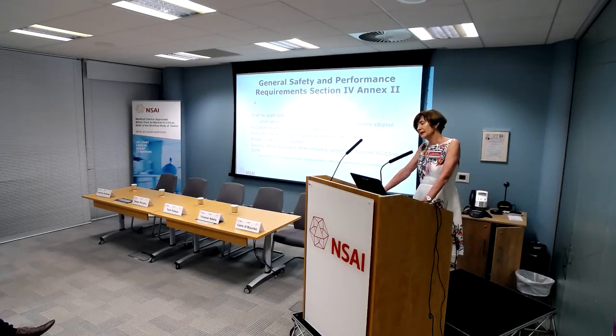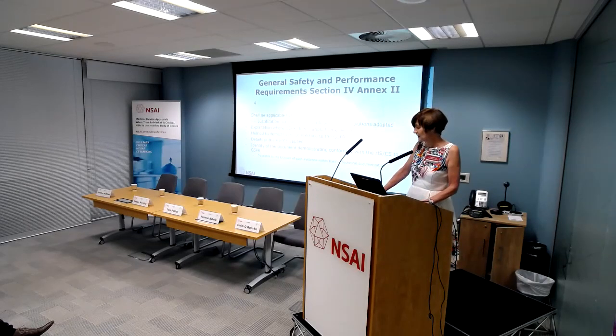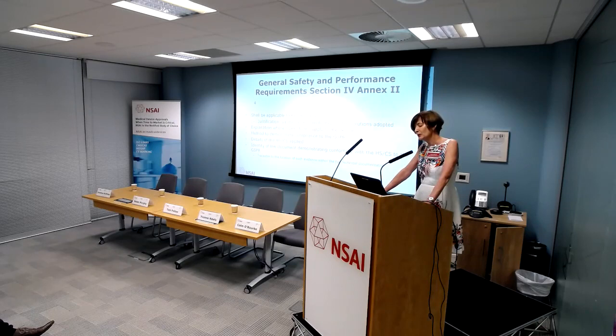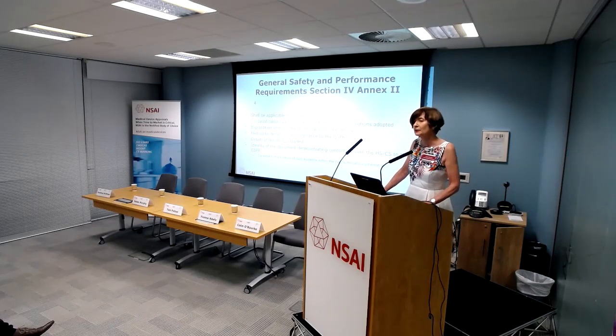You need to demonstrate the method, how you comply with the essential or the general safety requirements. You need to identify the harmonized standards and the common specifications that you have applied, together with the date of issue, because we will be looking for the most up-to-date version that you're in compliance with. And then we want you to document the identity of the document demonstrating conformance with those, and that has to be traceable to a location. And when we come on site to audit, the auditor will have that information, and they will go and say, okay, Mary, I want to see this document. And you say, where'd they get that from? It was in your tech file. So we want to make sure it is there.